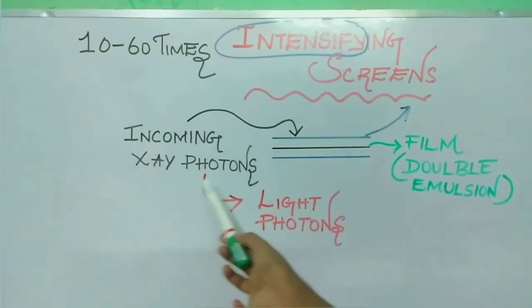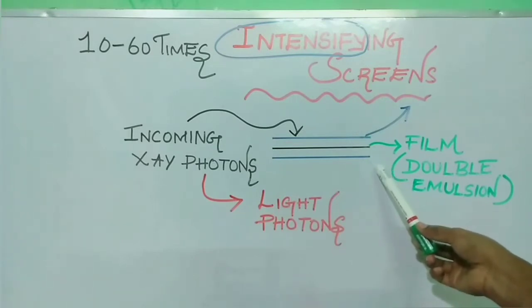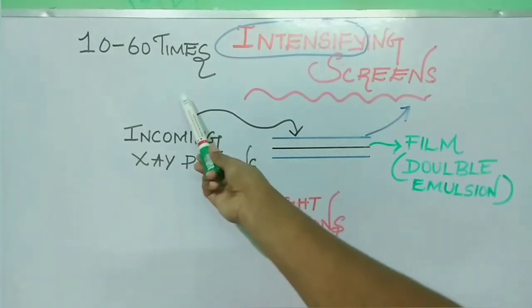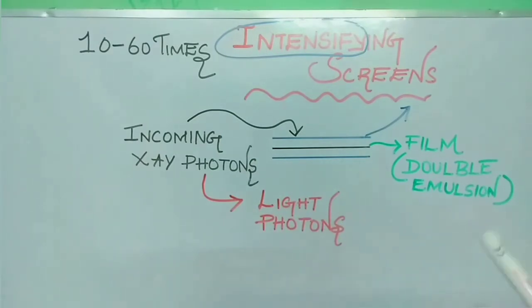They absorb incoming x-ray photons and re-emit this incoming x-ray energy in the form of light photons with the help of phosphor crystals in the intensifying screen. The amount of x-ray energy absorbed is directly proportional to the amount of x-ray energy to which the screen is subjected. So we are combining intensifying screens on either side of the film.